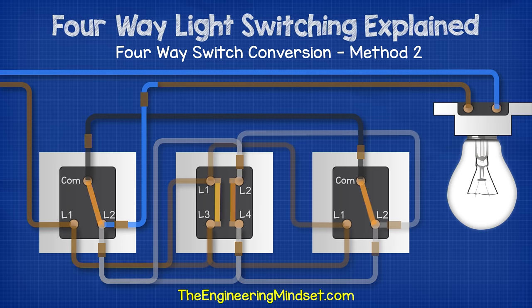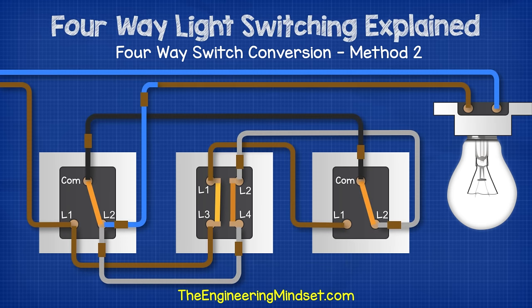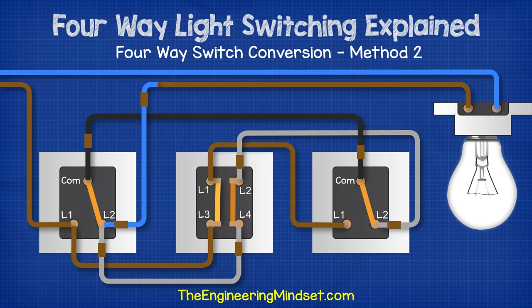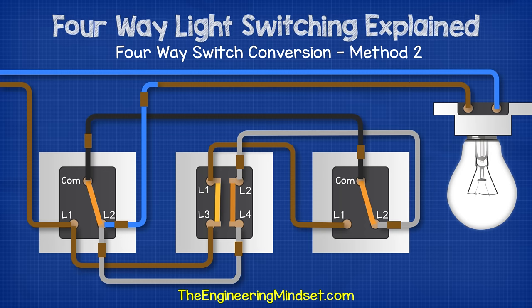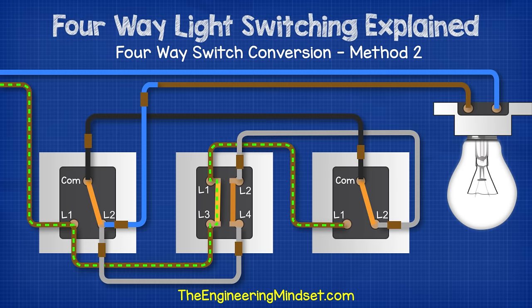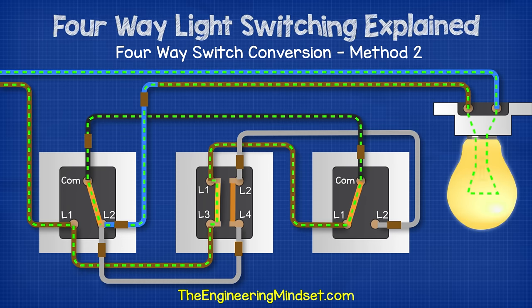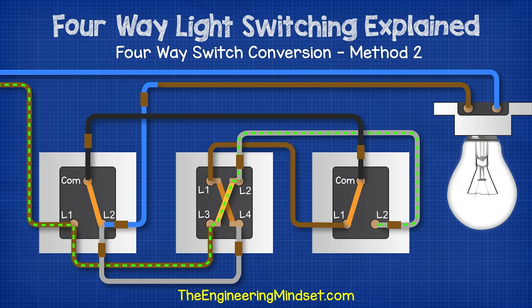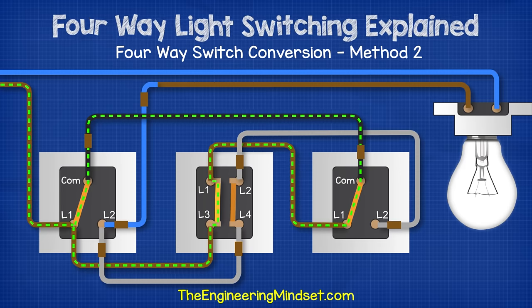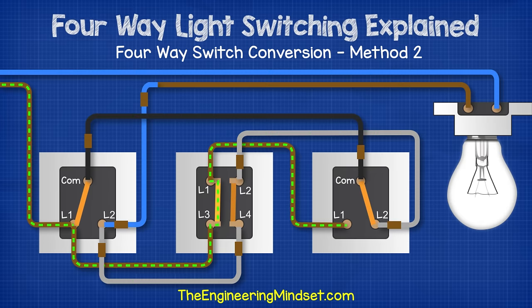The second method is a variation of the last one, using the same cables but changing their route slightly. We have the live into L1 of switch one, then a brown wire from L1 of switch one to L3 of switch two, and another brown wire from L1 of switch two to L1 of switch three. Then a gray wire from L2 of switch one to L4 of switch two, and another from L2 of switch two to L2 of switch three. We then have a black wire between the two commons, and finally the blue wire back to the lamp circuit. Flipping any switch in sequence makes or breaks the circuit.